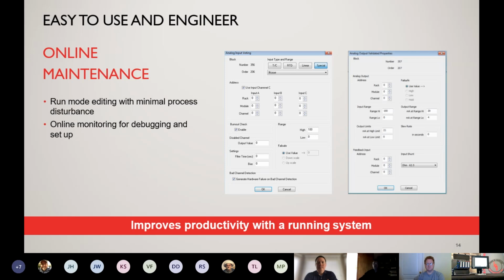I would just say in these instances where you want to do online editing, keep it somewhat simple. If you're going to be adding 5 control loops or 10 control loops and a bunch of other things, then yeah, you might want to shut the process down for those applications. And the HC900 will actually give you a warning, and it'll tell you if you're allowed to do that edit online. But this is a big differentiator because most PLCs are going to require you to do a cold start when you do a program change, and that means you have to shut down the processor, start the processor back up, and while you're doing that, obviously your process is shut down.